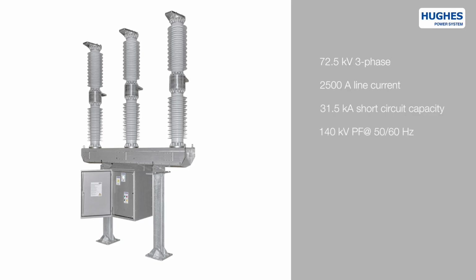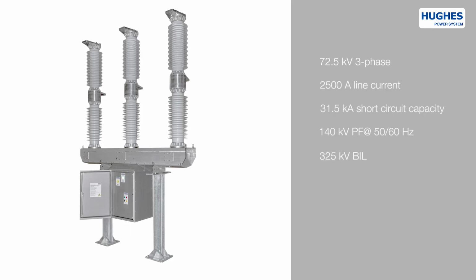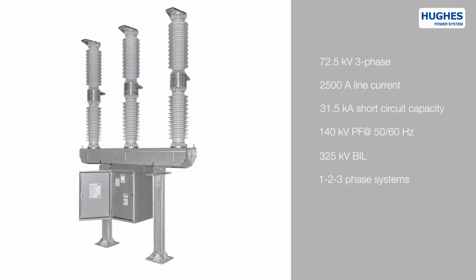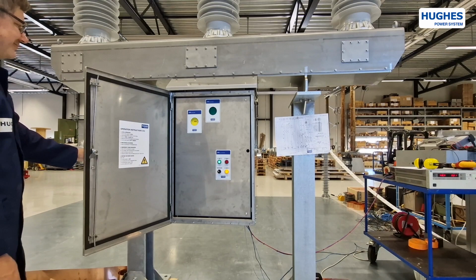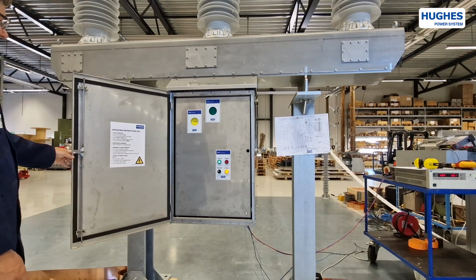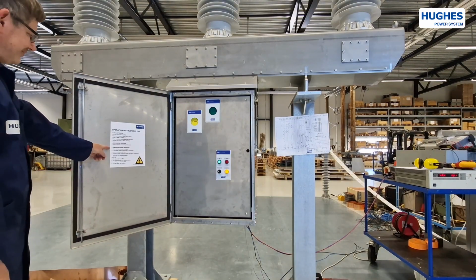140 kV power frequency at 50 or 60 Hz over open contact. Superior 325 kV basic insulation level. Solution for 1, 2, 3 phase systems. Anti-vandalism poles fitted with silicone polymeric insulators as standard. The cabinet is manufactured of the highest quality stainless steel. The external door contains the brief operational instructions.